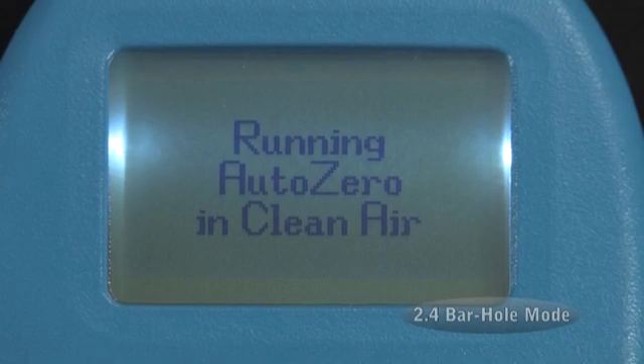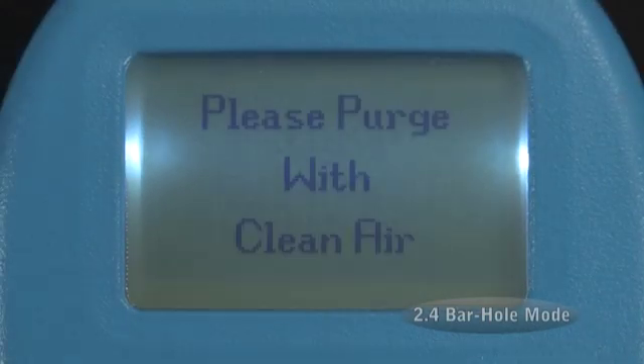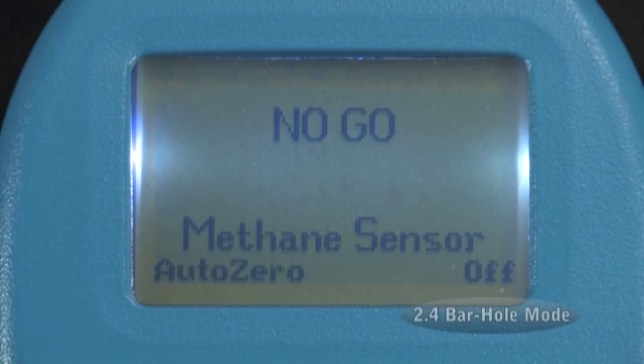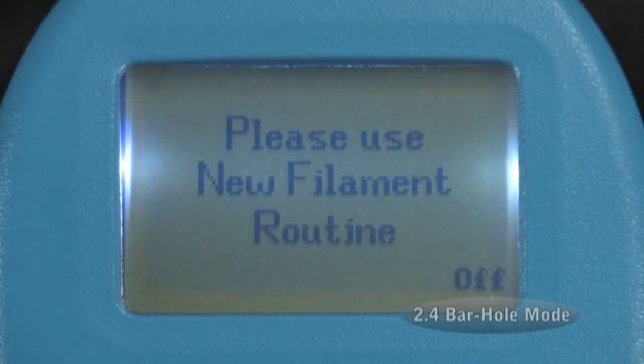If the Auto Zero is successful, it will return to the Please Purge with Clean Air screen, followed by the bar hole mode. If the Auto Zero finds gas, the detector will say No Go and will show which sensor or sensors measure gas. At this point, you have the option of retrying Auto Zero by again pressing the left button. If it fails again, you will be asked to run a new filament routine. Press the right button to turn the instrument off, then run the new filament routine as described in Section 3.5, Troubleshooting and Replacing Sensors.